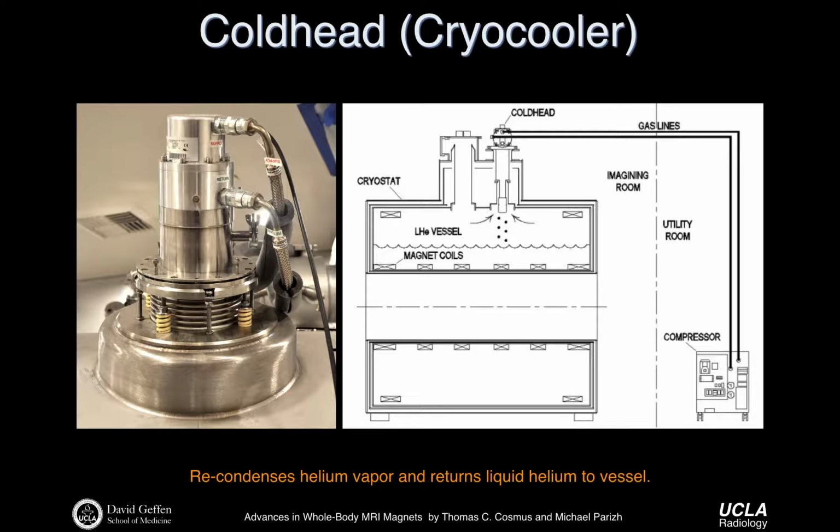And so as an MR scientist, you're always really sensitive to noticing if the cold head is operational and running when you get into the MR suite. If it's not, that's a problem, because it means that your system is probably losing helium, and if it loses enough helium, it can warm up enough, and then you have this positive feedback cycle that results in a quench, the loss of helium.